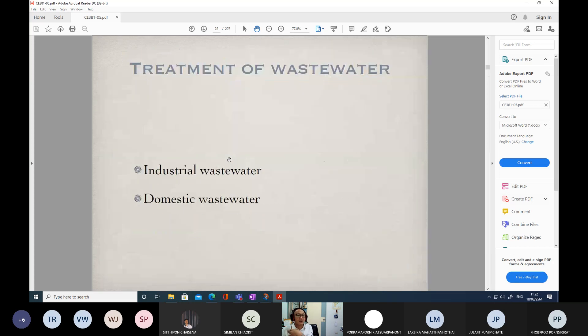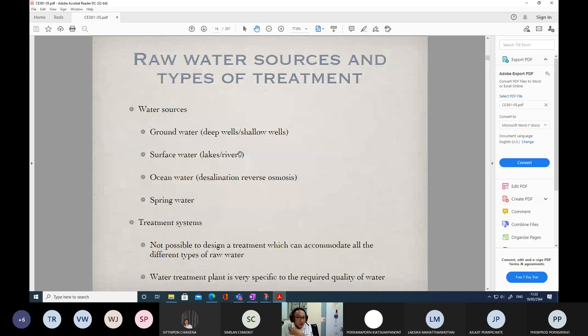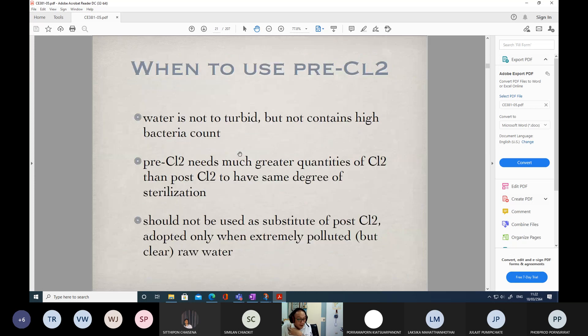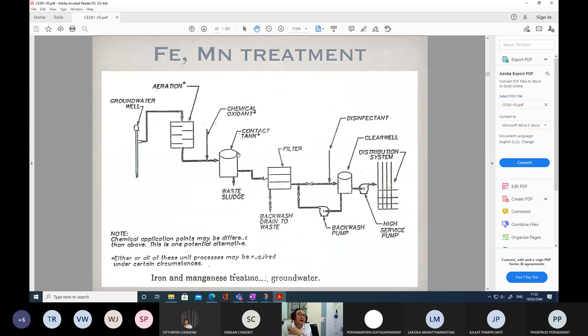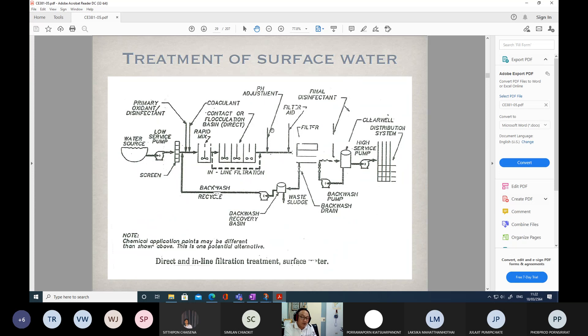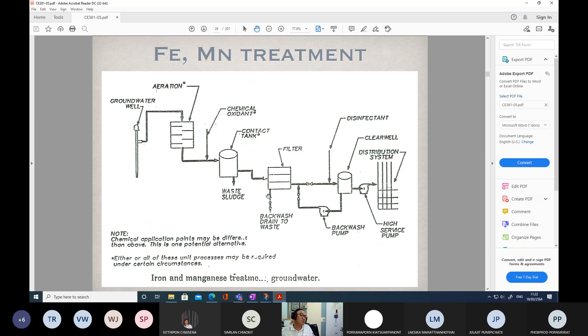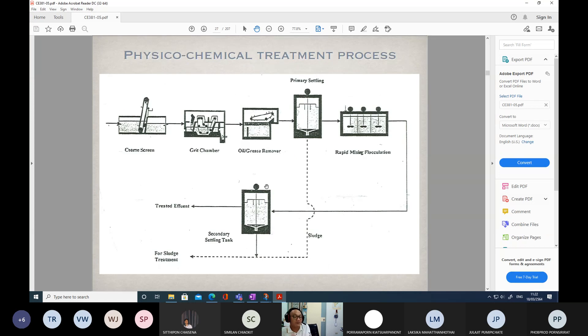Sometimes pH adjustment may be required if we use coagulants that need a very specific pH range — low or high — so before proceeding to the next unit processes, we need to adjust pH back to the neutral range. After the filter, we have a clear well, which is a chamber used to keep the produced water. In this chamber, disinfectant is also added. These are all the typical aspects of a water treatment plant.